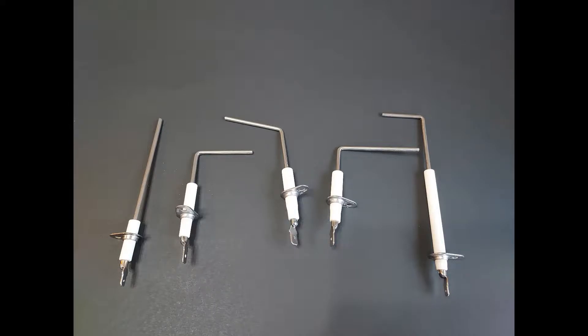The most common furnace issue that I find in the winter is a dirty flame sensor. So the majority of the time, all they need is a little cleaning. They do go bad, but it's rare.